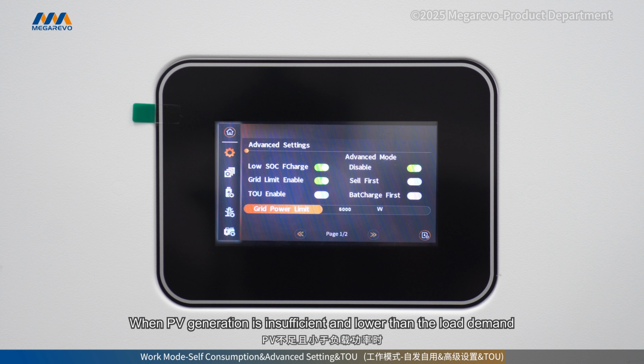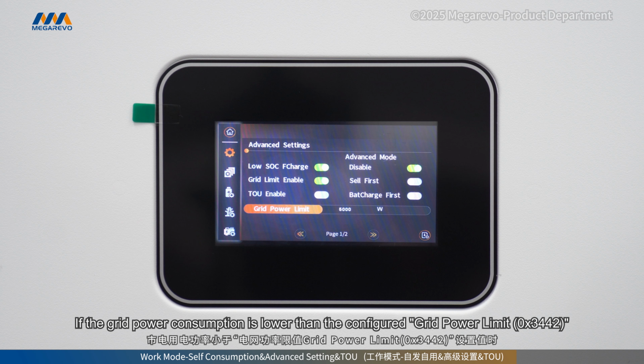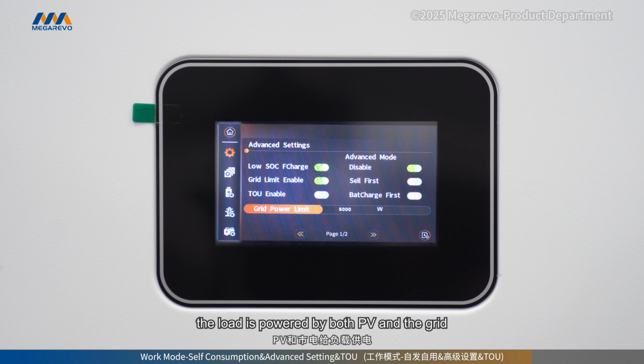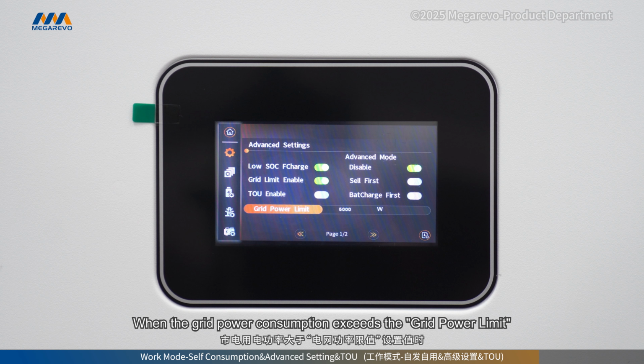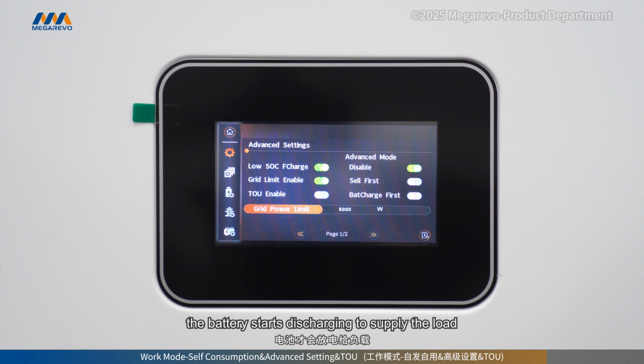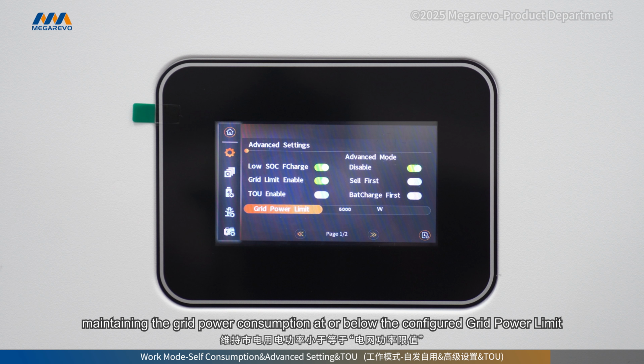When PV generation is insufficient and lower than the load demand, the load will preferentially draw power from the grid. If the grid power consumption is lower than the configured grid power limit, the load is powered by both PV and the grid, and the battery does not discharge. When the grid power consumption exceeds the grid power limit, the battery starts discharging to supply the load, maintaining the grid power consumption at or below the configured grid power limit.